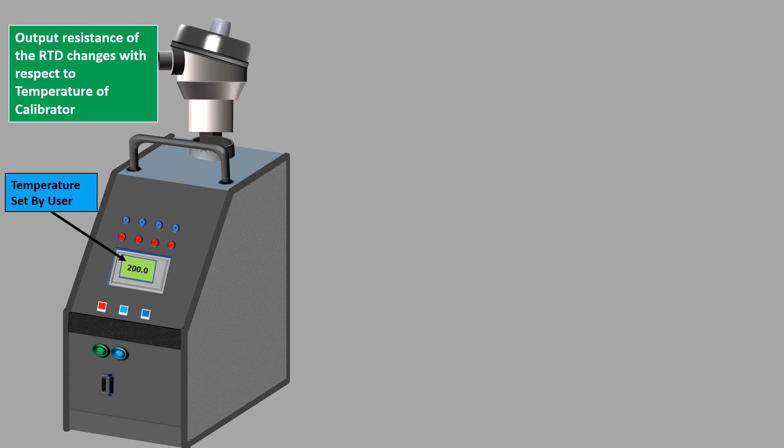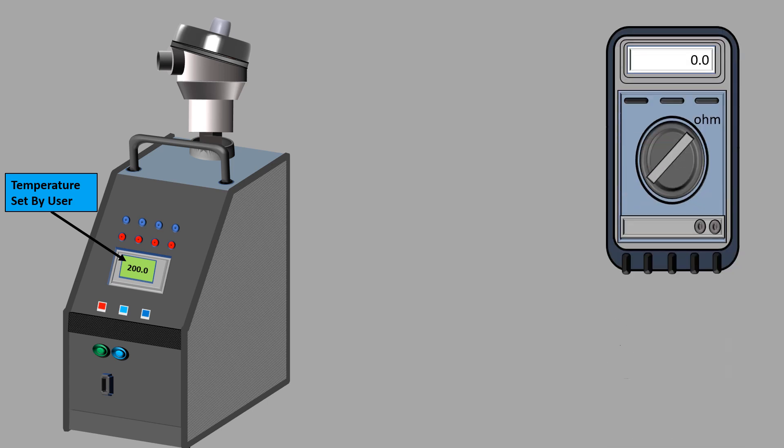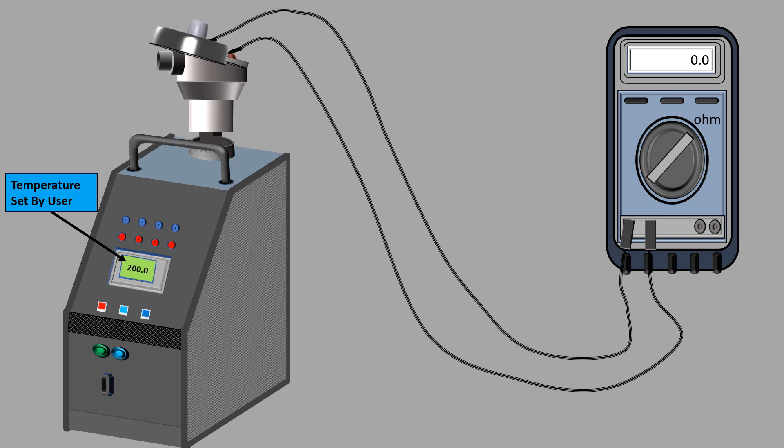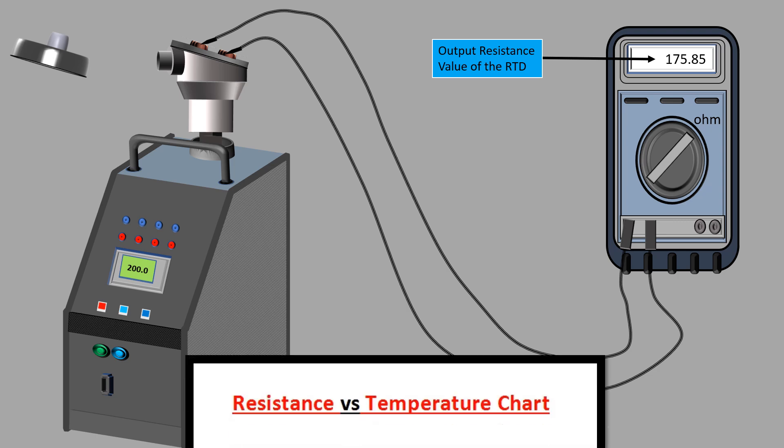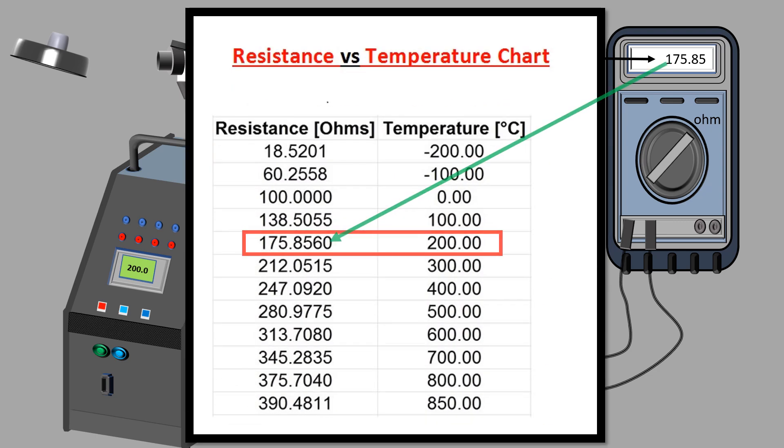A multimeter in resistance mode is connected between the terminals of the RTD to read the output resistance value of the RTD. This output resistance value is compared with the standard resistance versus temperature chart provided by the manufacturer to find the exact temperature detected by the RTD.